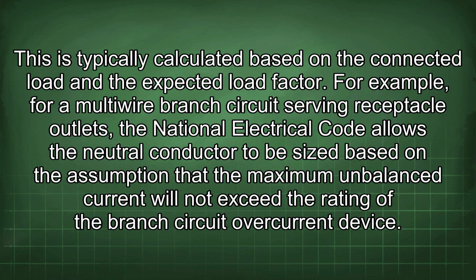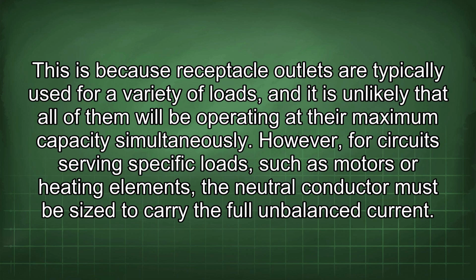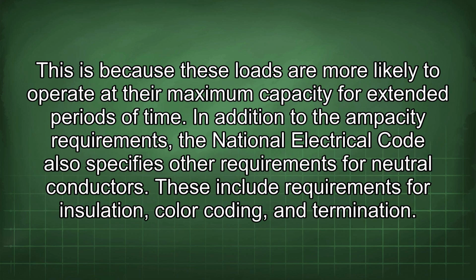For example, for a multi-wire branch circuit serving receptacle outlets, the National Electrical Code allows the neutral conductor to be sized based on the assumption that the maximum unbalanced current will not exceed the rating of the branch circuit overcurrent device. This is because receptacle outlets are typically used for a variety of loads, and it is unlikely that all of them will be operating at their maximum capacity simultaneously. However, for circuits serving specific loads, such as motors or heating elements, the neutral conductor must be sized to carry the full unbalanced current. This is because these loads are more likely to operate at their maximum capacity for extended periods of time.